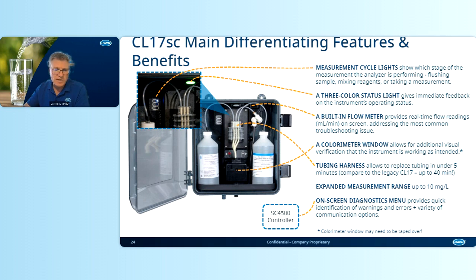The colorimeter window provides another visual aid to see what the colorimeter is doing right now, whether the stir bar is in place, whether the color is being developed, so it's easy to watch visually if the reagents are delivered and the color is developed. In some situations, when there is direct sunlight, which is absolutely not recommended for the installation, this window should be taped. Now, the tubing harness, that's the biggest part of consternation with the previous legacy CL17 analyzer. Now it's improved enormously. We created a tubing harness, which is pre-assembled and can replace all the tubing along with reagents in a matter of minutes.